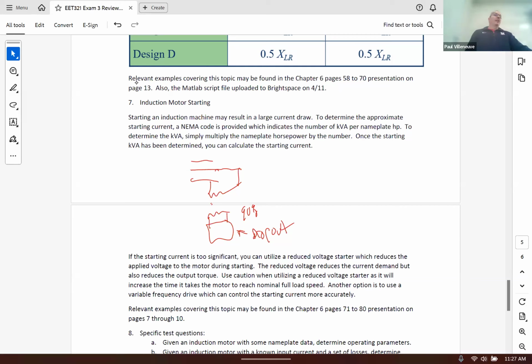And you can go to GE, you can go to Siemens, you can go to ABB and look at their motor control centers, and they have all kinds of options, but one of the options is low voltage. And it's an auto transformer, so you can change what starting values you want. You can have it start at 65% voltage, 85% voltage. And the reason why they give you those varying values is the lower the voltage, the longer it's going to take to start.